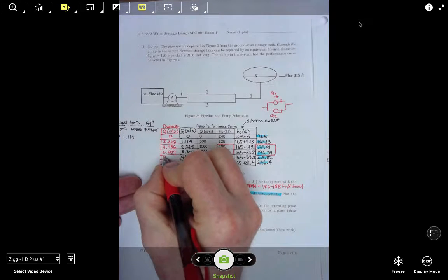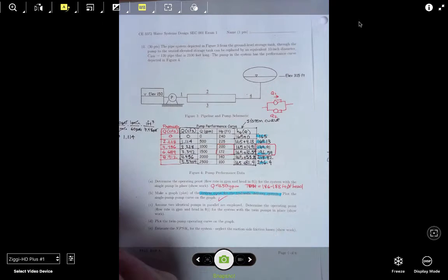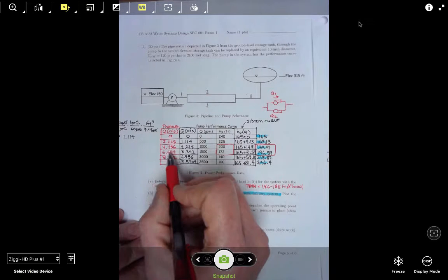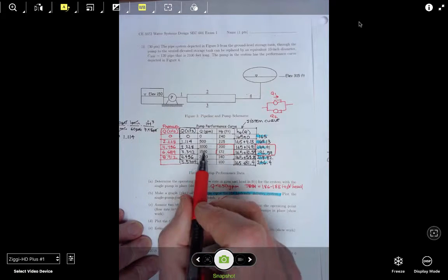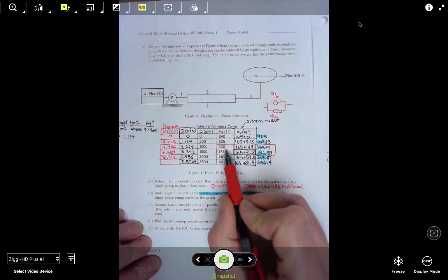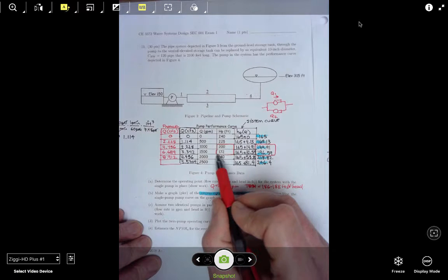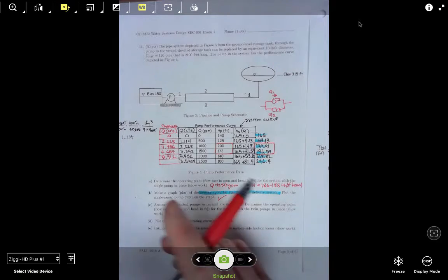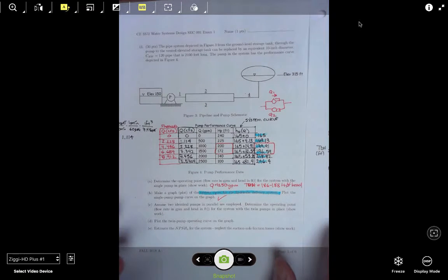I'm pretty sure that we're not going to get much outside of here. So now here's what we have. We still have the pump providing between the intersection. The head part doesn't change, but now the curve has moved to the right. So let's plot the new pump curve for the twin pumps in parallel, and then we'll see roughly where the flow rates fall.